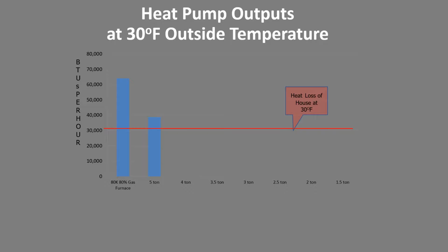We see that the 5-ton gives you almost 40K. The heat loss is around 30K, so we could say that's oversized. The 4-ton gives you a nice fit. The 3.5-ton hits it perfectly. The 3-ton hits it perfectly. The 2.5-ton starts to fall short, then 2, and then just a little bit ridiculous, the 1.5 tons. So this is one way to think of balance point. You're just basically seeing what the heat loss is at 30 degrees, and then double checking what the capacity of the equipment is at 30 degrees and trying to get as close to each other as possible.